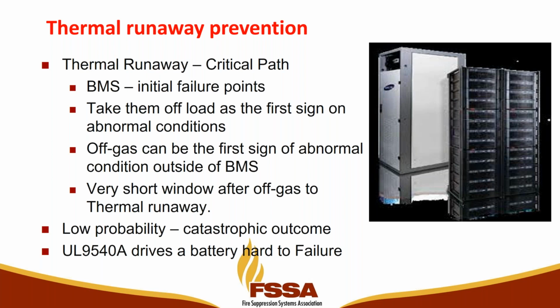But of course, we don't put fire systems in for things that work right 100% of the time. So these are redundant backup systems in case the BMS doesn't do its job. There is a very short window from off-gas to thermal runaway. It could be seconds, it could be minutes, depending upon the failure mode. This 9540A test, where they basically burn a bunch of batteries and push them hard to failure, is something you're not going to normally see in the industry.